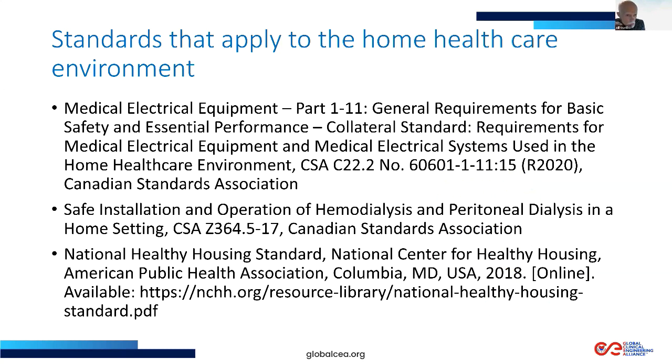60601-1-11 does have requirements for medical equipment and electrical systems used in the home healthcare environment. I challenge you to find anyone supplying home healthcare equipment that really knows about this standard.